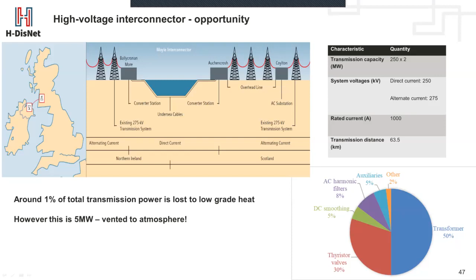When you break down the way a system works, the losses are mainly across the transformer and the thyristor valves within the system, and that's where we focused our work. What you have in the center is a stack of thyristors, held within a room that is air conditioned to 15 degrees centigrade, with humidity kept as low as possible. The reason to keep humidity low, and the reason it's air conditioned, is to prevent corona discharges from one side of the thyristor set to the other.